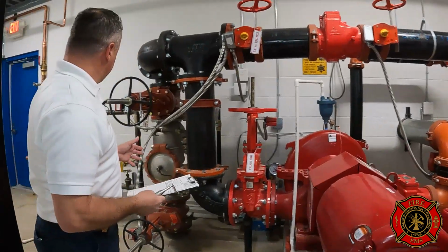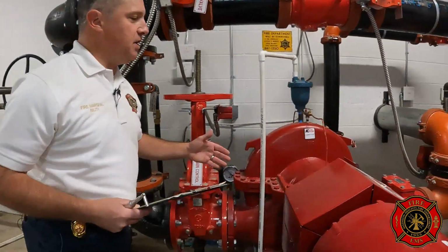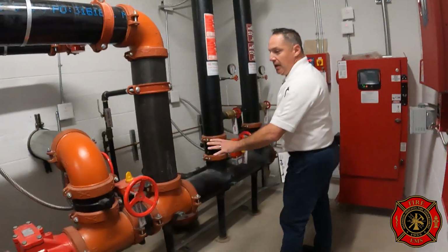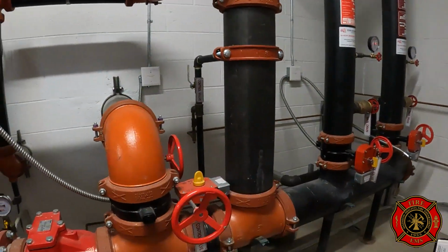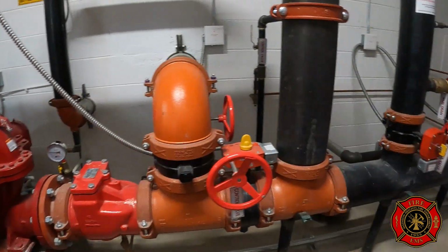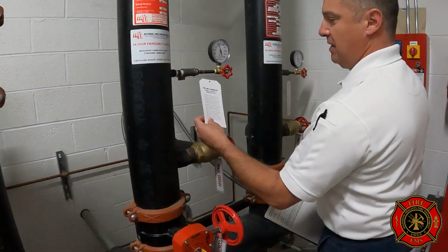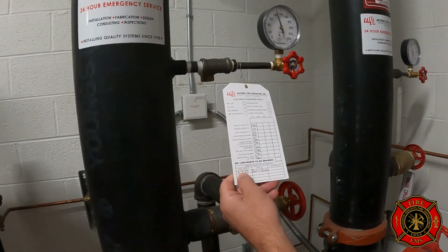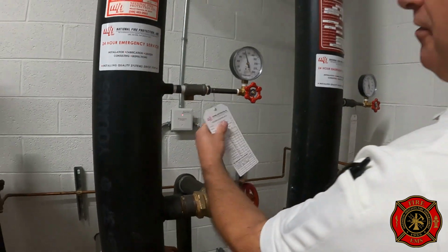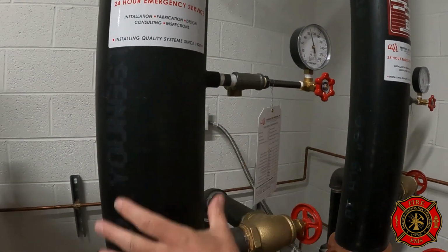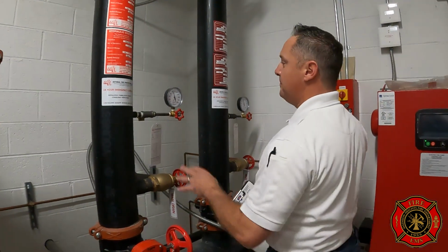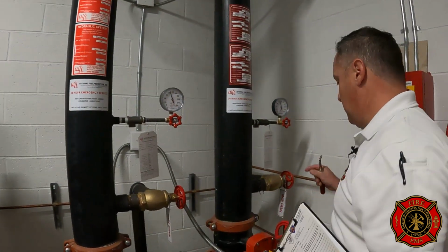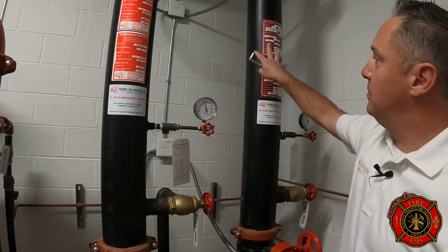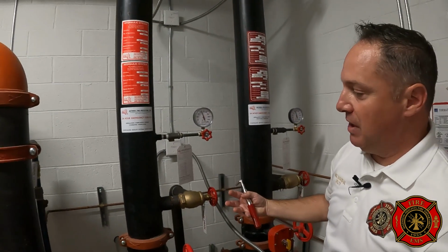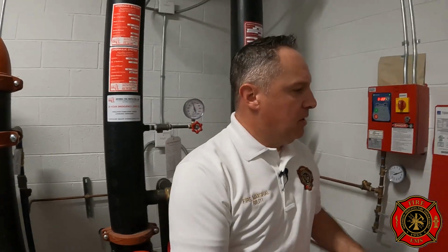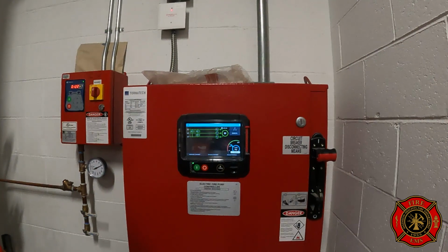So some of the things I'm looking for is where it comes in from the city, which is going to be over this way. It goes through this large apparatus and pumps and builds up that pressure. What I'm looking for is the last time it was inspected. So I'll come over to this tag, and 6/7 of 22, a third party, National Fire Protection, came out and certified this system. That has to be done annually. I'll take a look at the pressures inside. There is the pressure that is inside the sprinkler system right now, and then the pressure at what it's coming in from the city. This is kind of the brains of the operation. This is their fire pump.